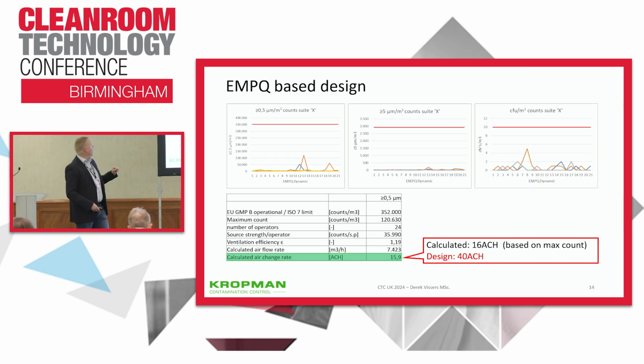So what we did, we took this data, the peak value, the maximum counts for particles, for example for 0.5 micron, and then you can calculate the actual source strength during the EMPQ. We also know the ventilation efficiency from the recovery time measurements, and then you can calculate how much air was actually required in my clean room. That's not 40 air changes per hour, but only 16 air changes per hour based on the source strength data from max counts, the worst case scenario. If you take the average values, it's only 5 air changes per hour. So the system is really over-designed.